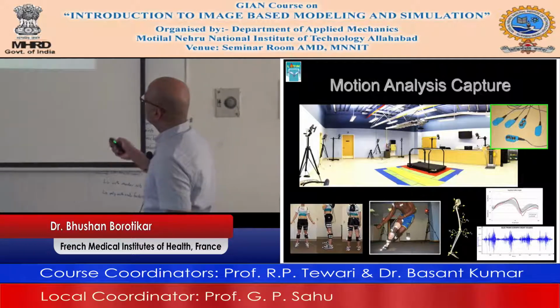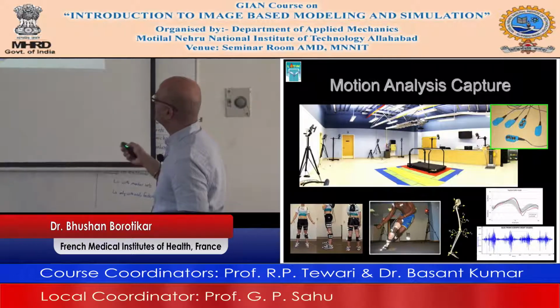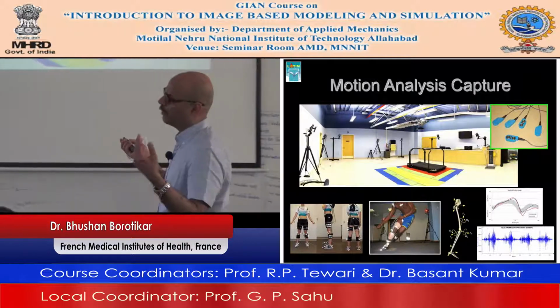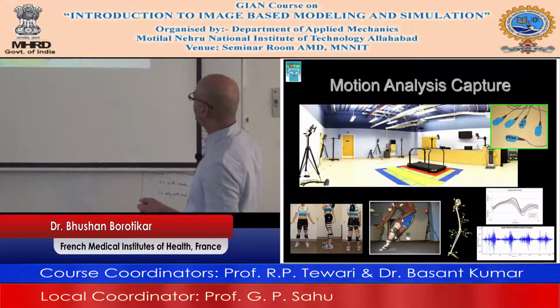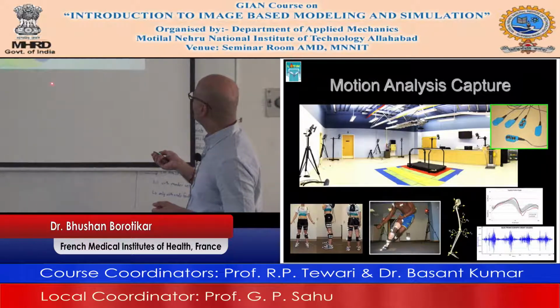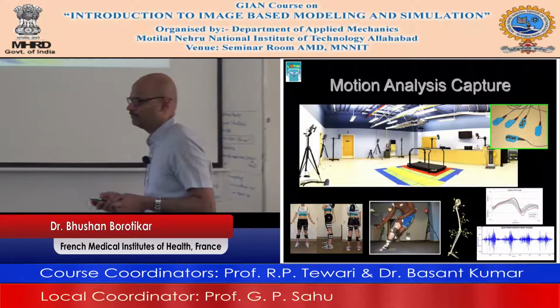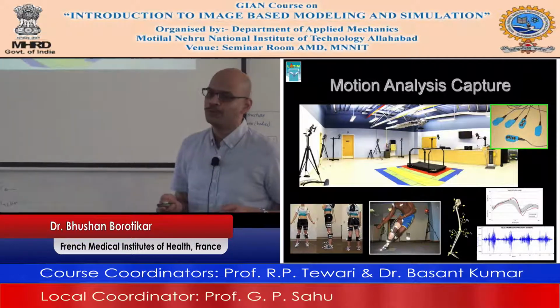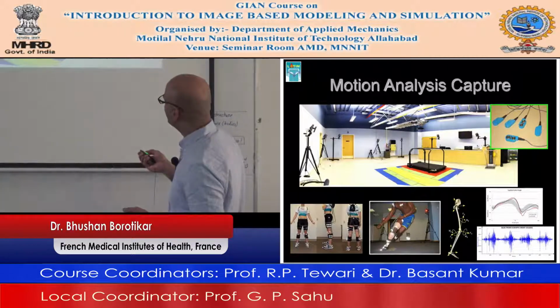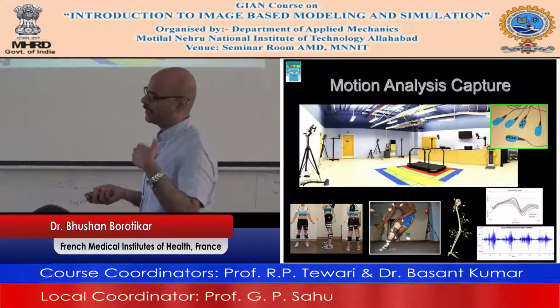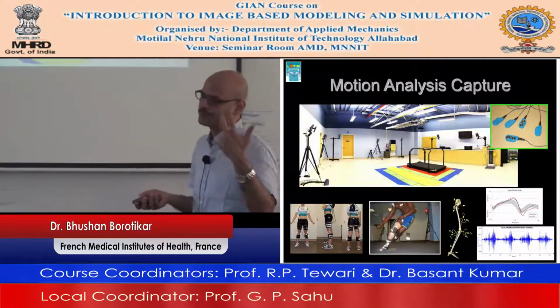Here, these are the infrared cameras. In a typical state of the art motion analysis system, there are 8 or more cameras surrounding. Here are instrumented treadmills, where if you want to do running studies, the belt of the treadmill is embedded with force plates. So, when you walk, you would get all the forces of walking. When you run, you will get forces of running.